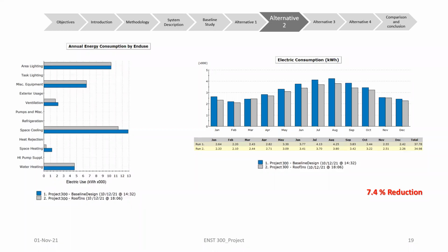Here, the first figure shows that adding insulation to the roof has led to a noticeable decrease in the overall annual energy consumption as compared to the base case. The electric load related to lighting, electrical equipment, and water heating, as I stated before, has not been affected by the roof insulation, since they are considered internal heat gains. The load related to cooling, heating, and ventilation showed a considerable decrease due to the addition of the roof insulation. This decrease is higher than the decrease obtained when insulating all the exterior walls, because the main contributor to the increase in heat gains is the solar heat gain. The solar rays are incident perpendicularly to the roof, whereas they have a certain incident angle at the wall surface. So, the effect of solar rays is more pronounced at the roof than at the walls. In conclusion, the electric consumption shows a decrease of 7% when using this alternative compared to the base case.